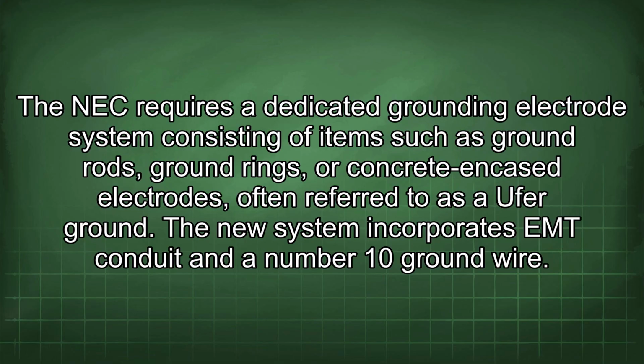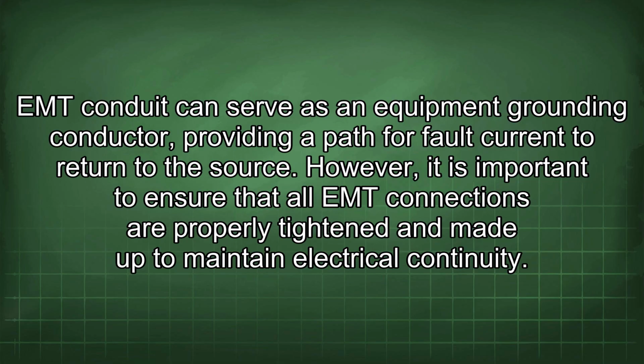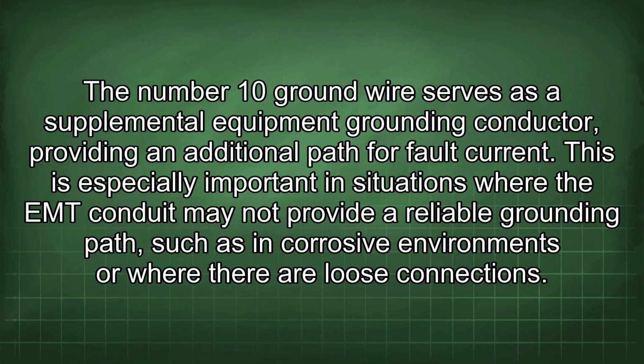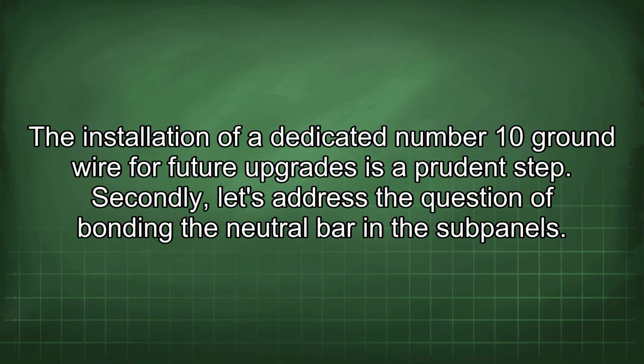The new system incorporates EMT conduit and a number 10 ground wire. EMT conduit can serve as an equipment grounding conductor, providing a path for fault current to return to the source. However, it is important to ensure that all EMT connections are properly tightened and made up to maintain electrical continuity. The number 10 ground wire serves as a supplemental equipment grounding conductor, providing an additional path for fault current. This is especially important in situations where the EMT conduit may not provide a reliable grounding path, such as in corrosive environments or where there are loose connections. The installation of a dedicated number 10 ground wire for future upgrades is a prudent step.